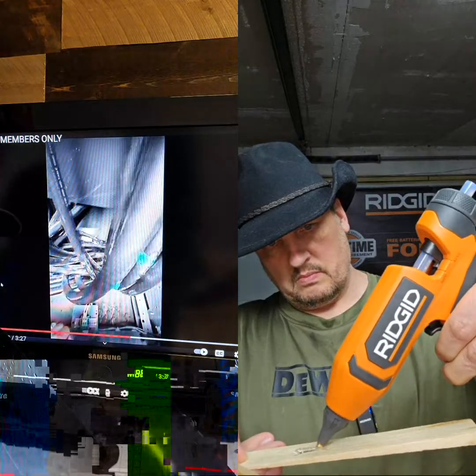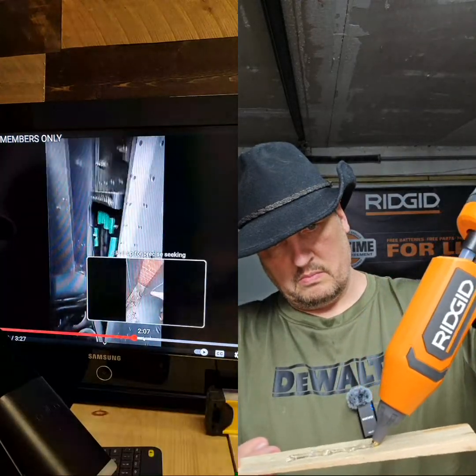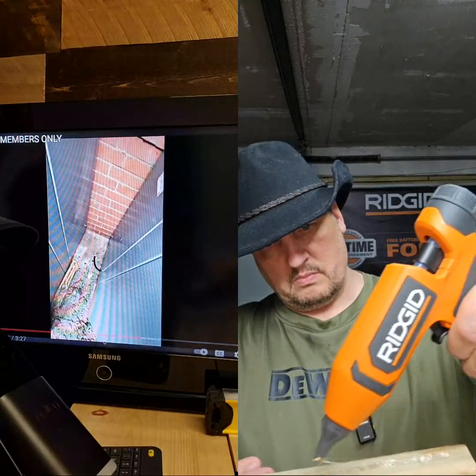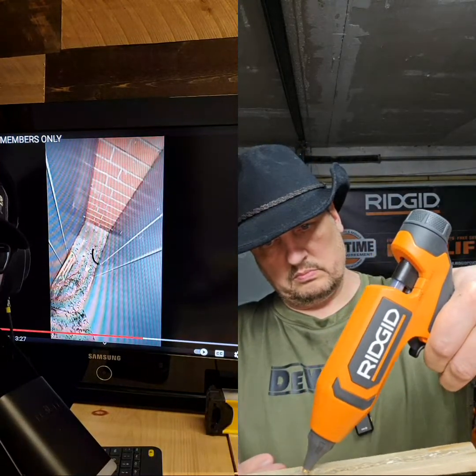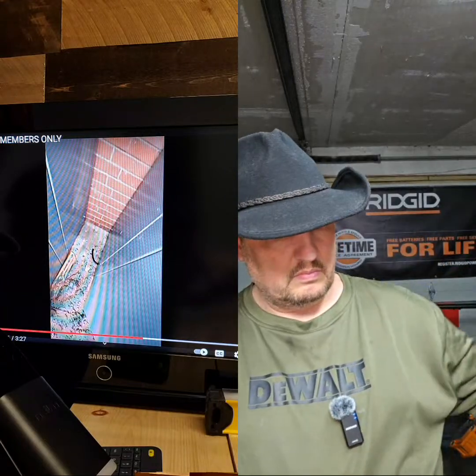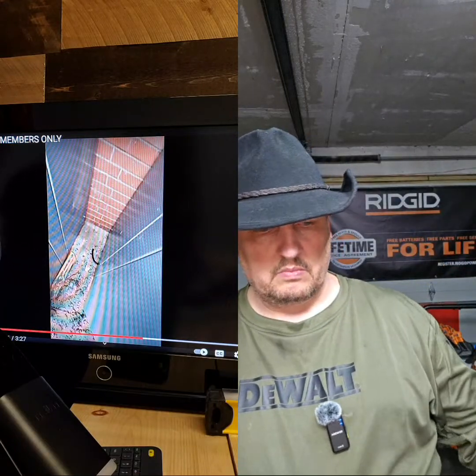Here we go, 5 grounds there, 5 pipes for the load. We got 1 ground here, follow it, it goes to a ground rod. So he just ran it to a ground rod. Didn't run it to the building steel, didn't run it to the cold water, didn't run it to anything. Just put it in the ground.